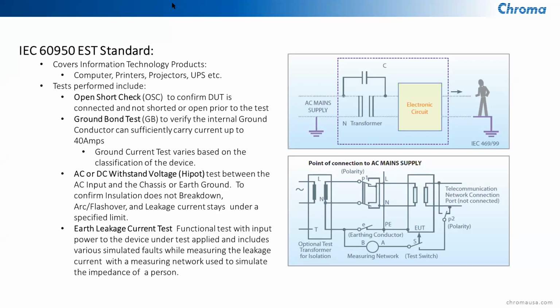I got a question about your AC/DC withstand voltage hipot testers. What kind of current does it put through when you charge your system for, say, 1,000 volts? Because I'm not looking forward to potentially damaging any of my systems if I perform this test. Sure. Well, we can program that current level from microamps to milliamps, and it can be done accurately based on whatever the standard requirement is. We have high current levels that will give you up to 120 milliamps, or down to as low as a few microamps. So it is programmable. It is something that you can do, limiting the amount of current through your device.